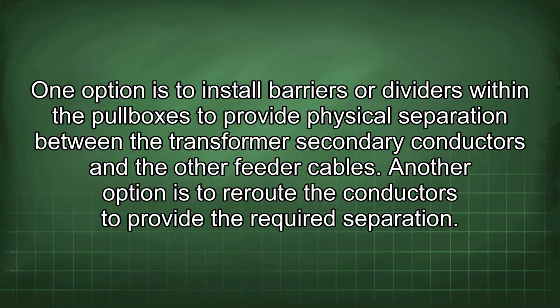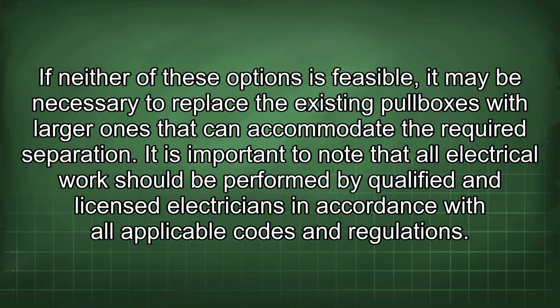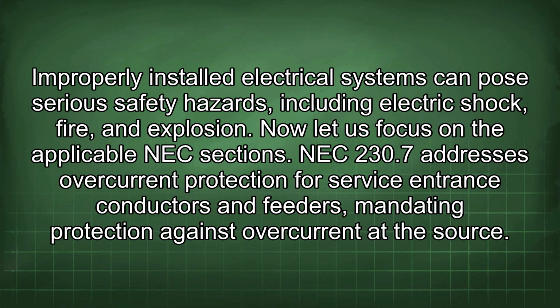One option is to install barriers or dividers within the pullboxes to provide physical separation between the transformer secondary conductors and the other feeder cables. Another option is to reroute the conductors to provide the required separation. If neither of these options is feasible, it may be necessary to replace the existing pullboxes with larger ones that can accommodate the required separation. It is important to note that all electrical work should be performed by qualified and licensed electricians in accordance with all applicable codes and regulations. Improperly installed electrical systems can pose serious safety hazards, including electric shock, fire, and explosion.